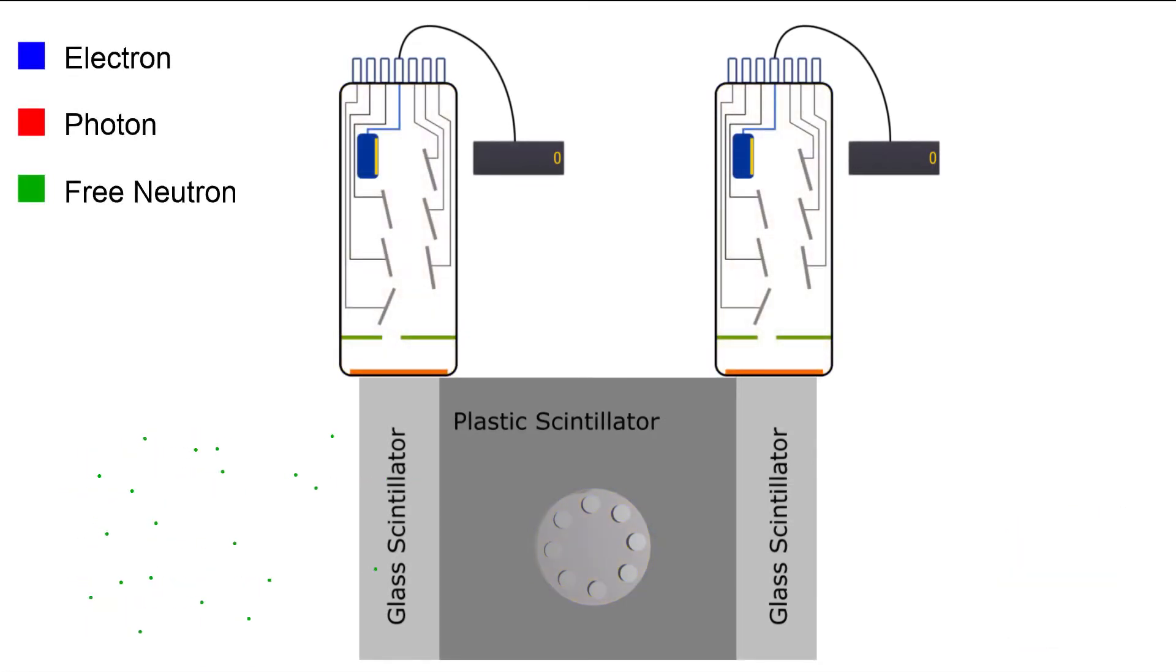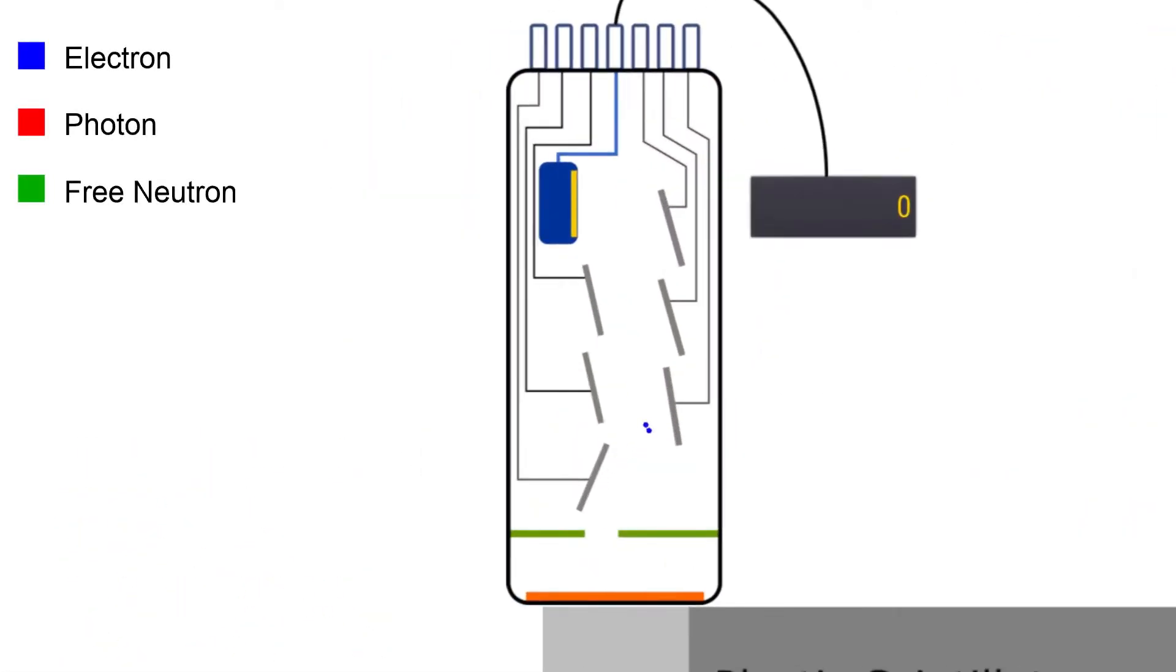The photons created by this interaction are directed to hit the first stage of a photomultiplier tube. This causes electrons to be released. These electrons then hit the next stage of the photomultiplier, which causes more electrons to be released. These go on to hit more stages, releasing even more electrons for every stage.